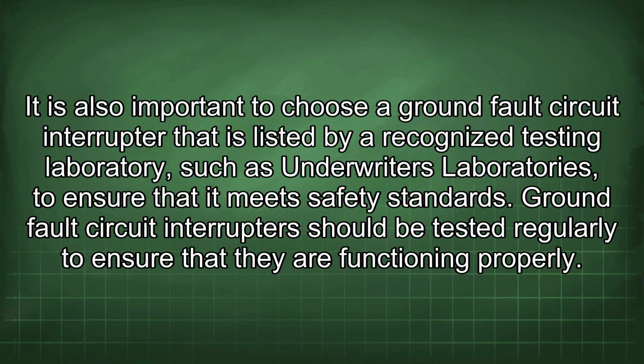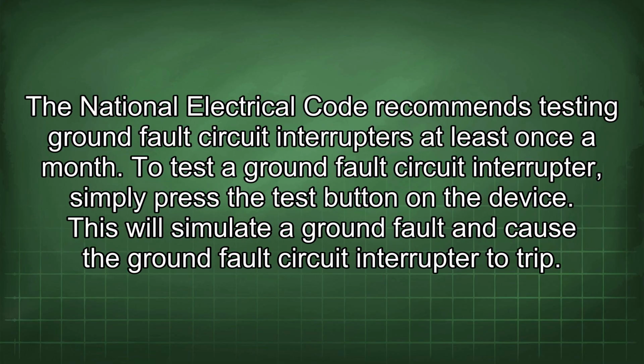It is also important to choose a ground fault circuit interrupter that is listed by a recognized testing laboratory, such as Underwriters Laboratories, to ensure that it meets safety standards. Ground fault circuit interrupters should be tested regularly to ensure that they are functioning properly. The National Electrical Code recommends testing ground fault circuit interrupters at least once a month.